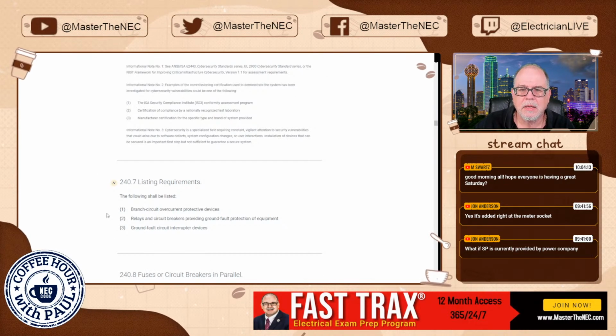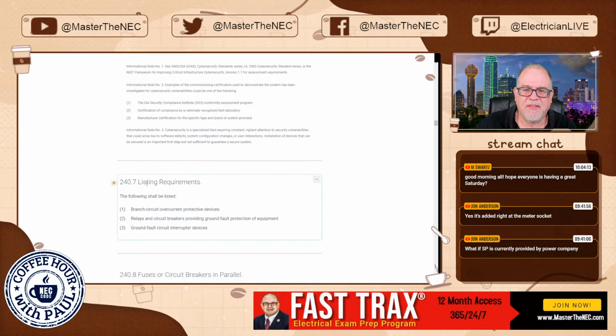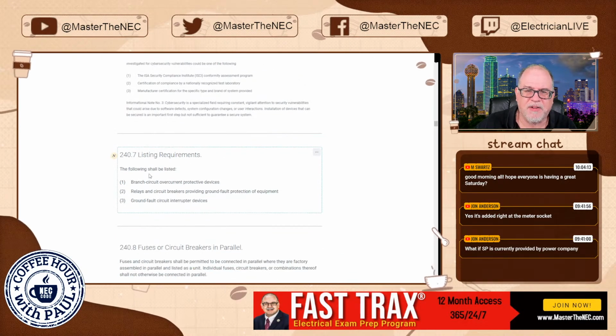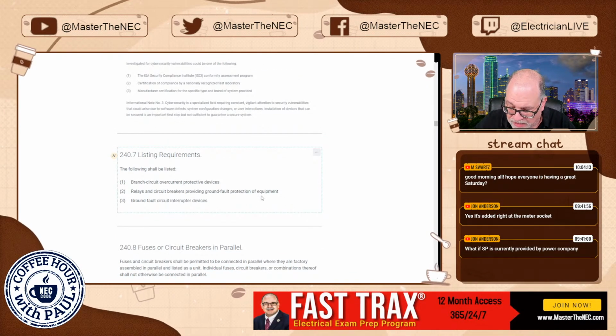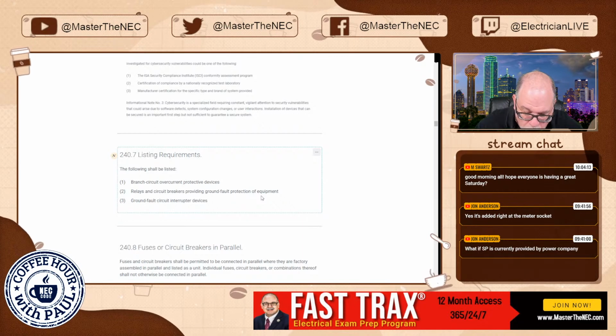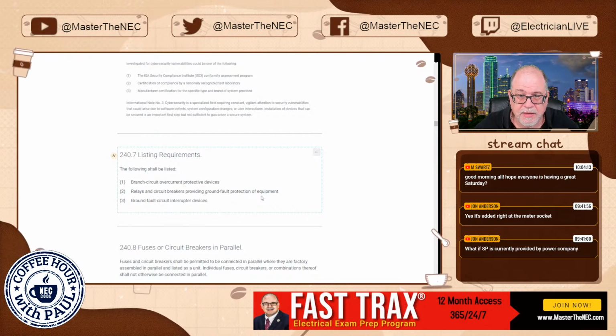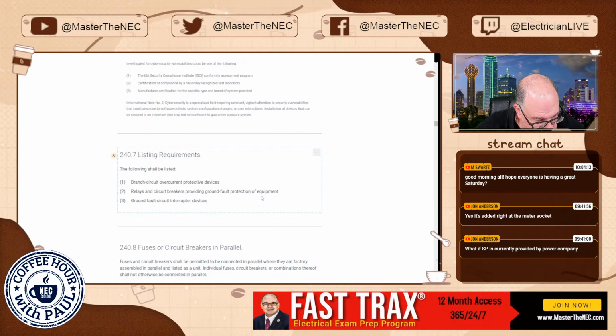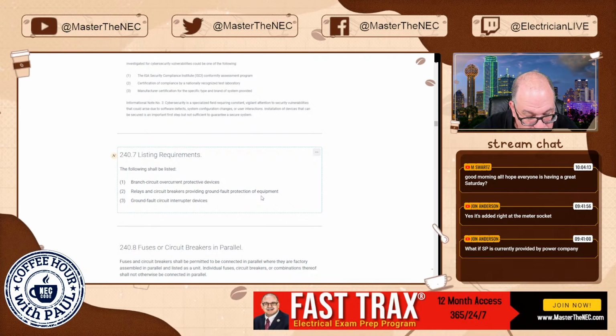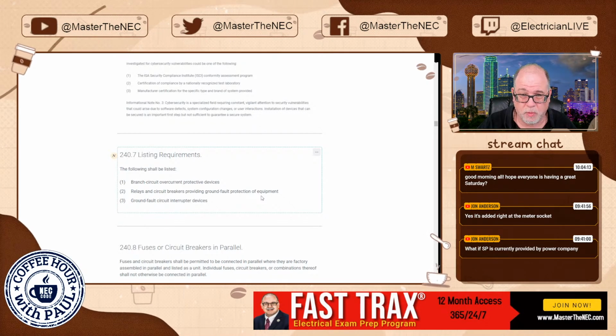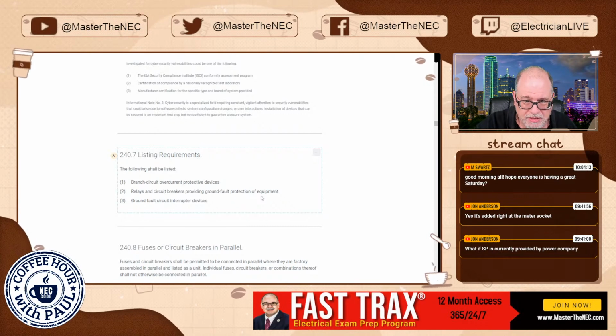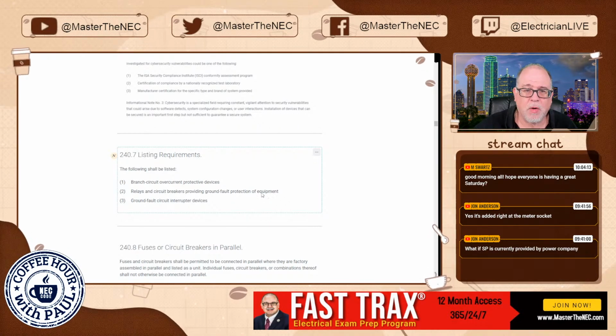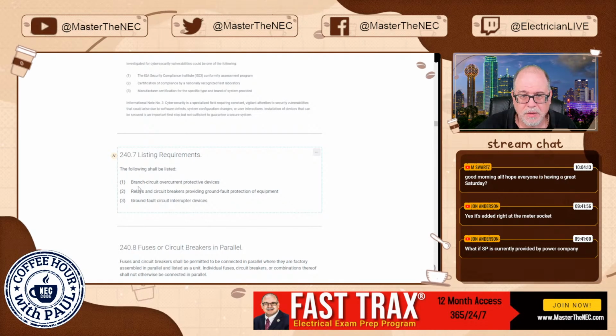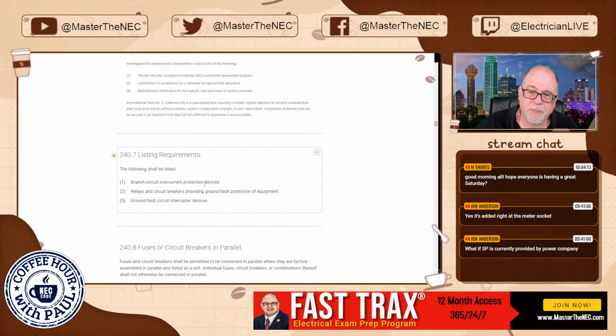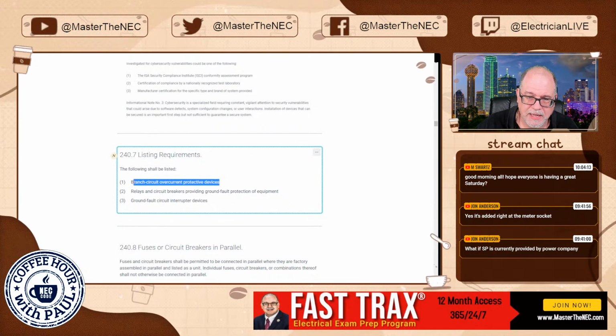All right. Let's see, 240.7 listing requirements. The following shall be listed. Now, if I were to take my code book and go look at 240.7, okay, now this says new, but if I go look at 240.7, you'll notice that we don't have a 240.7. So we have some listing requirements here. So what's required to be listed under 240? Well, branch circuit overcurrent protective devices, they got to be listed.